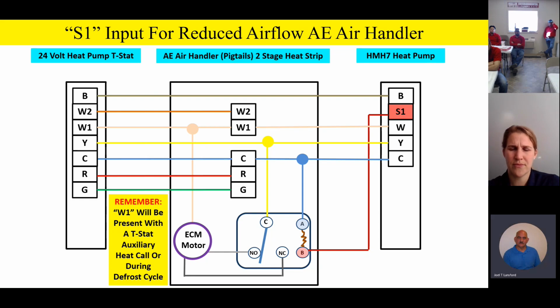That's a good question. Not specifically. So what's going to drive the outdoor unit when we go to defrost will be at 100%. But if we're cruising along, say at a 70% capacity, and we get an auxiliary heat call, that W1 call will not drive the outdoor unit to 100%. And so that's a good question. That's a fine point there.